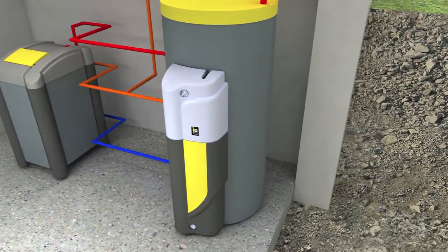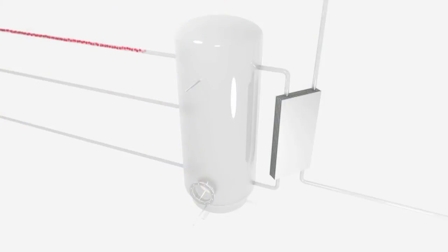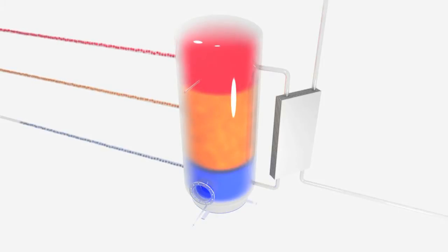The rest is used for general heating to 35 degrees centigrade. The red HGL pipe delivers water at 60 degrees centigrade to the buffer tank and heats it together with the orange colored flow from top to bottom. A speed controlled pump pumps hot heating water through the plate heat exchanger, providing controlled heating of the hot domestic water.